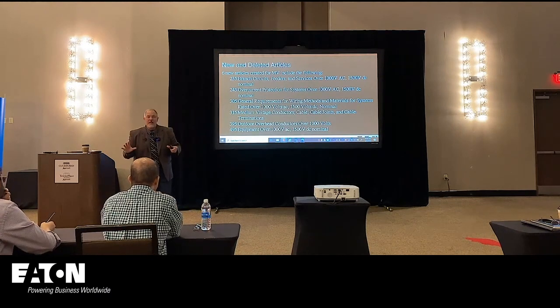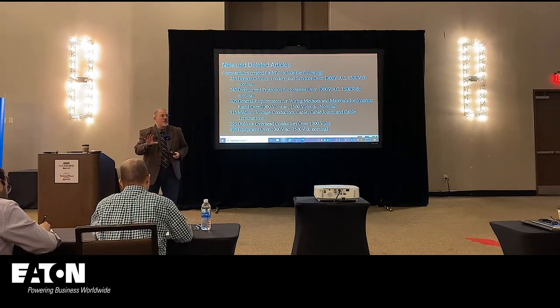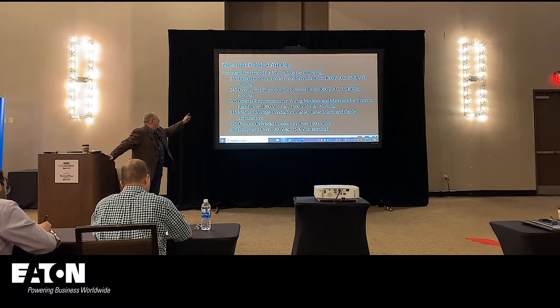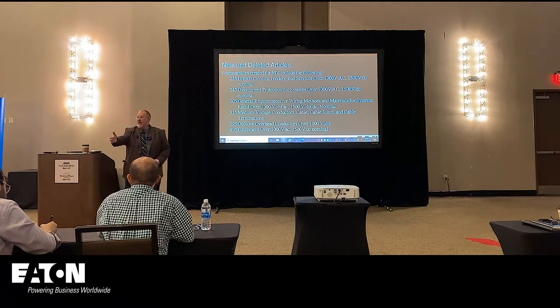And quite frankly, if you are worried about what the changes are, technical changes didn't occur this cycle. All they did was move. They couldn't make technical changes because it was in the second draft, and you can't introduce new material. 245 is your overcurrent protection. So they took the contents of 240 that applied to medium voltage and moved it to 245.